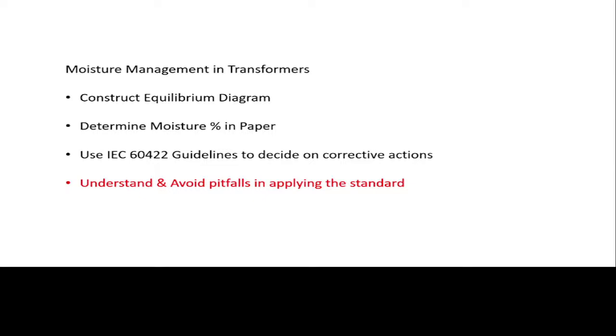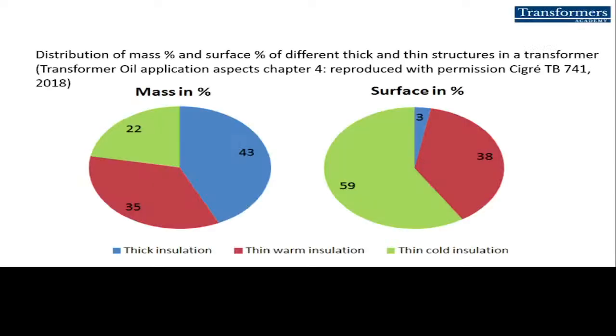I will talk a little bit about moisture management in transformers. Basically, we have to understand the moisture equilibrium, the moisture migration effects, and avoid the pitfalls in applying the standard. There are standards available, but standards are not going to help because you are talking about a dynamic process which is constantly changing. The moisture is constantly changing its position.